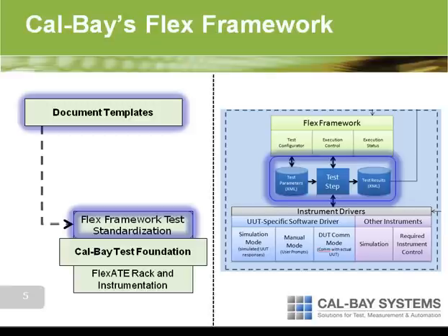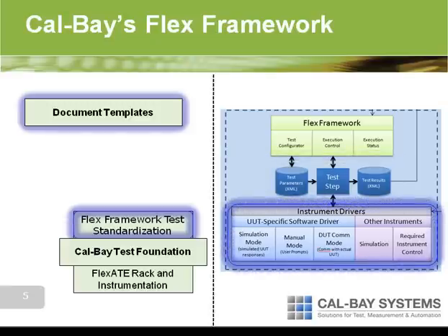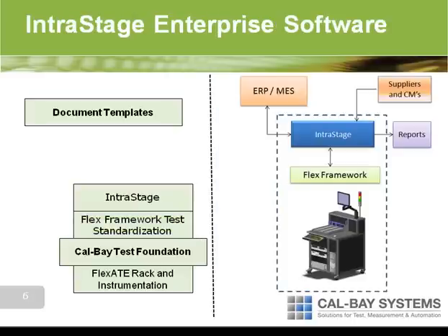The next standard is instrument class drivers and UUT drivers. The Flex Framework uses an object-oriented approach that allows for instrument simulation and the interchange of instruments. The test steps are written to talk to instrument classes rather than to specific instruments, which has 2 key benefits. First, the instrument drivers are truly plug-in components, so any Flex Framework driver can be added to a system and immediately used without code modification of the test steps or test scripts. Second, the instrument drivers have a defined way to simulate, so that the developers can make progress on test step code even if they don't have access to instruments or UUTs. The Flex Framework software ensures that each ATE is running properly and writing results to file.